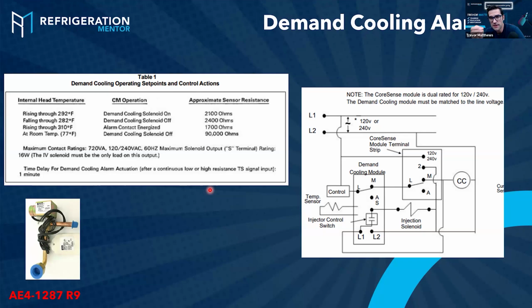That sensor is in the compressor, in the head of the compressor, and I'll show you where it looks right in the head, because the hottest part of any compressor is right at the discharge valves. And when those discharge, that last squish of gas right up there, that's the hottest part of any compressor. Okay, and when the temperature rises up high enough, it says solenoid on. And look, we see in here it says at 2100 ohms, that solenoid valve is on.